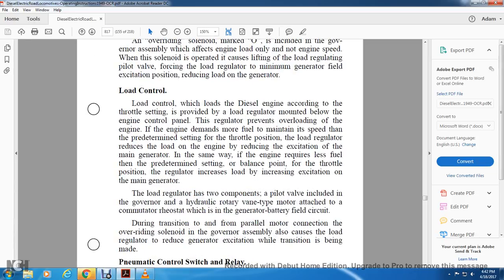Engine load control, which loads the diesel engine according to the throttle setting, is provided with the load regulator mounted below the engine control panel. The regulator prevents overloading of the engine. If the engine demands more fuel to maintain the speed of the predetermined setting of the throttle position, the load regulator reduces the load of the engine, reducing the excitation for the main generator. In the same way, if the engine requires less fuel for the predetermined setting, the balance point for the throttle position regulator increases load by increasing excitation on the main generator.